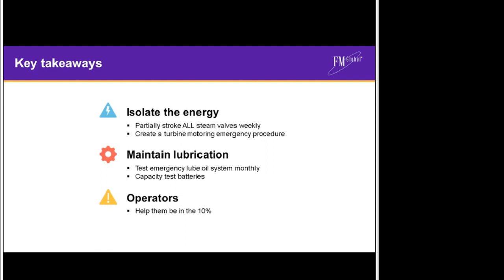Secondly, lubrication needs to be maintained. Emergency lube oil systems should be tested on a monthly basis to ensure that the emergency lube oil pump starts, and batteries should be capacity tested on a 2-yearly basis for valve-regulated lead acid batteries and on a 5-yearly basis for flooded lead acids or NICADs. And finally, but probably most importantly, operators need to be given every assistance they possibly can to help them be in the 10% that make a positive difference in an upset condition.